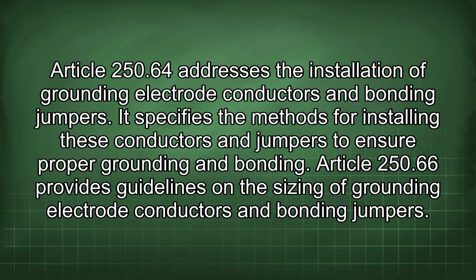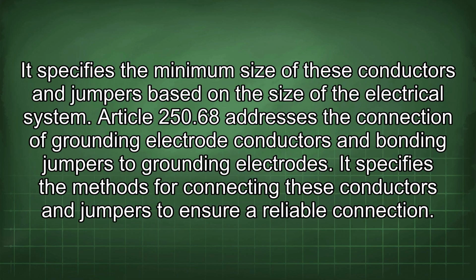Article 250.64 addresses the installation of grounding electrode conductors and bonding jumpers. It specifies the methods for installing these conductors and jumpers to ensure proper grounding and bonding. Article 250.66 provides guidelines on the sizing of grounding electrode conductors and bonding jumpers. It specifies the minimum size of these conductors and jumpers based on the size of the electrical system.